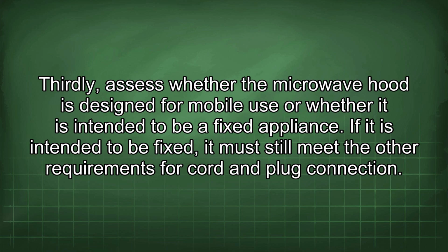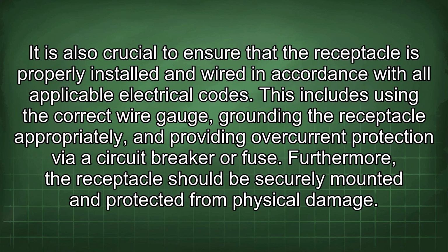be a fixed appliance. If it is intended to be fixed, it must still meet the other requirements for cord and plug connection. It is also crucial to ensure that the receptacle is properly installed and wired in accordance with all applicable electrical codes. This includes using the correct wire gauge, grounding the receptacle appropriately, and providing overcurrent protection via a circuit breaker or fuse. Furthermore, the receptacle should be securely mounted and protected from physical damage.